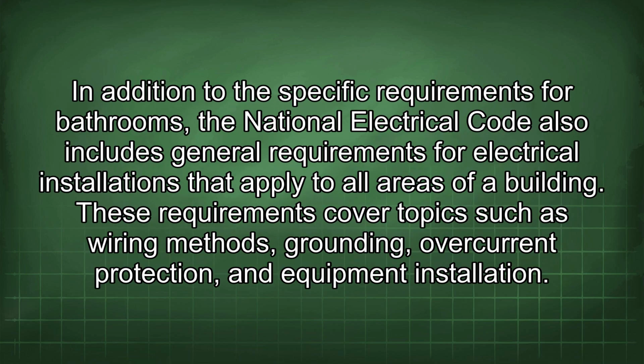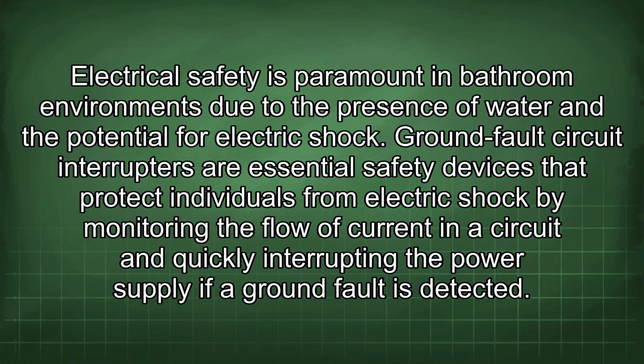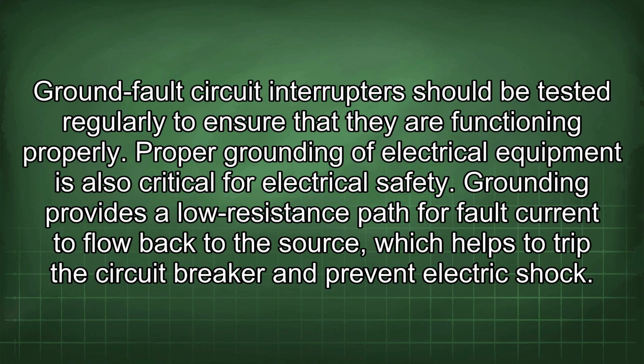In addition to the specific requirements for bathrooms, the National Electrical Code also includes general requirements for electrical installations that apply to all areas of a building. These requirements cover topics such as wiring methods, grounding, overcurrent protection, and equipment installation. Electrical safety is paramount in bathroom environments due to the presence of water and the potential for electric shock. Ground fault circuit interrupters are essential safety devices that protect individuals from electric shock by monitoring the flow of current in a circuit and quickly interrupting the power supply if a ground fault is detected. Ground fault circuit interrupters should be tested regularly to ensure that they are functioning properly. Proper grounding of electrical equipment is also critical for electrical safety.